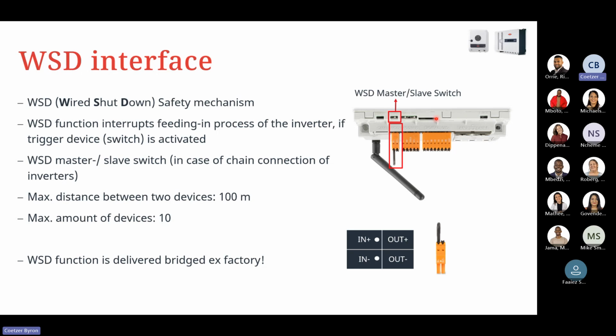Lastly is your WSD interface, your wired shutdown interface that's available as a safety mechanism. It's bridged from factory, and this allows us to use up to 10 devices with one master being responsible for your e-stop that's been triggered. We can have the distance between two devices being 100 meters and below. So it allows us to do up to 1 kilometer in total between the master and our last slave if we are using this WSD interface.